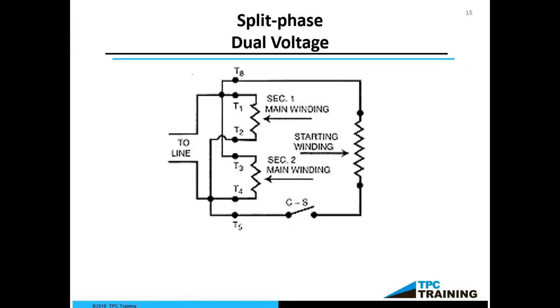Now, we're still looking at a single-phase motor, but this motor is dual voltage, just like the one on the nameplate we saw a little bit ago. Basically, we have our starting winding, which is way over here to the right again, to help us start the motor. No capacitor in this motor, it didn't need one, but we have our centrifugal switch there. And then what we have over here to the left, where we see T1, T2, T3, T4, that is our main winding. We divided it up in half, just like I mentioned before.